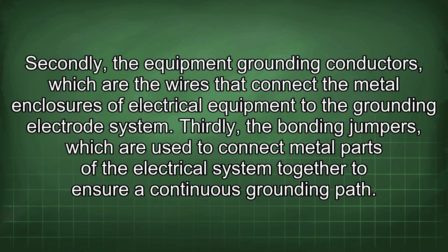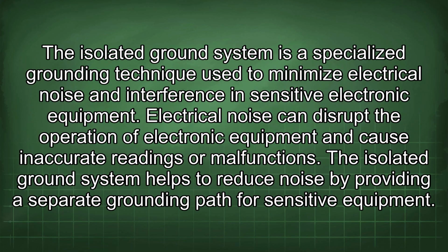Thirdly, the bonding jumpers, which are used to connect metal parts of the electrical system together to ensure a continuous grounding path. The isolated ground system is a specialized grounding technique used to minimize electrical noise and interference in sensitive electronic equipment. The electrical noise can disrupt the operation of electronic equipment and cause inaccurate readings or malfunctions. The isolated ground system helps to reduce noise by providing a separate grounding path for sensitive equipment.